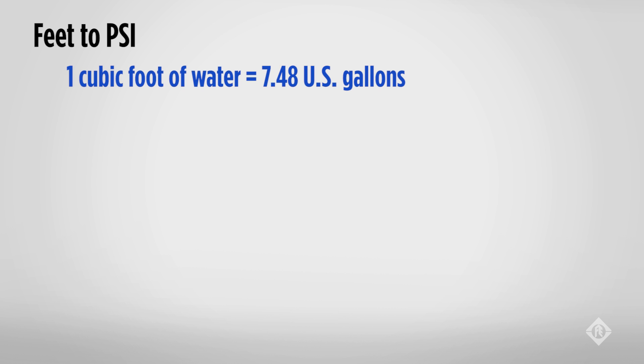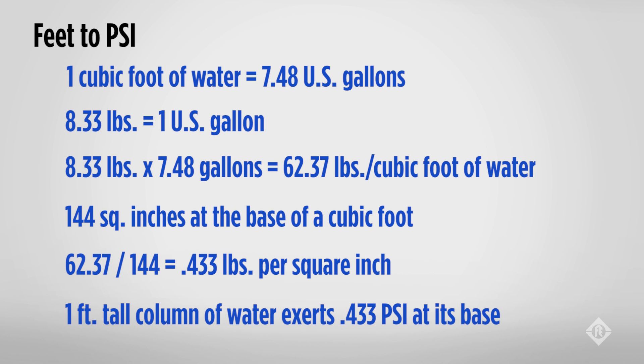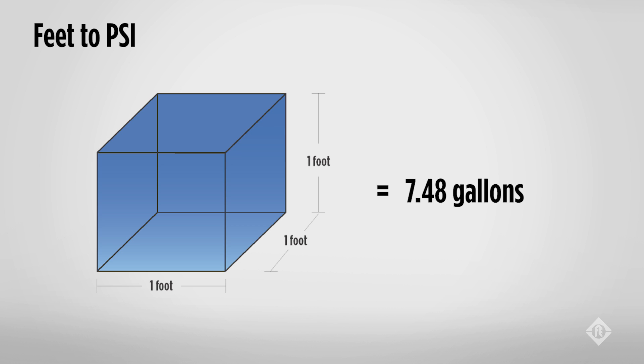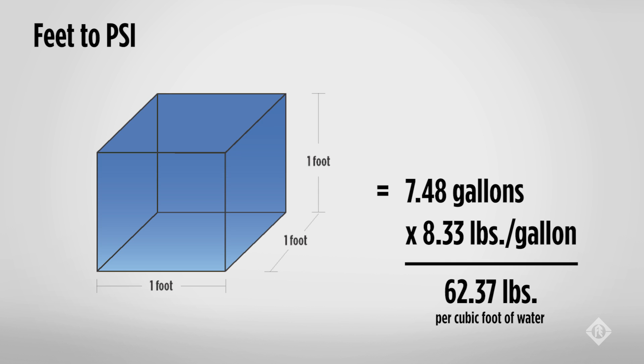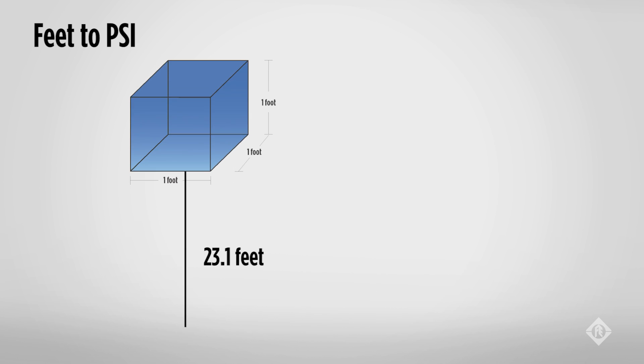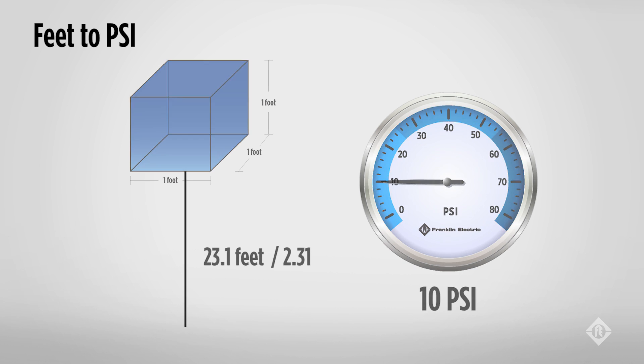So why this exercise? As we size pumps and plumbing, we will work between feet of head and psi routinely and need to be familiar with the units and where they come from. With 1 cubic foot of water holding 7.48 gallons, and the weight of 1 gallon of water being 8.33 pounds, we get 62.37 pounds per cubic foot of water. Don't become confused with mass and pressure — if we lift 1 cubic foot of water to 23.1 feet of elevation, we will only generate 10 psi of pressure at the bottom, as opposed to the 62.37 pounds of mass that we lifted up in the air.